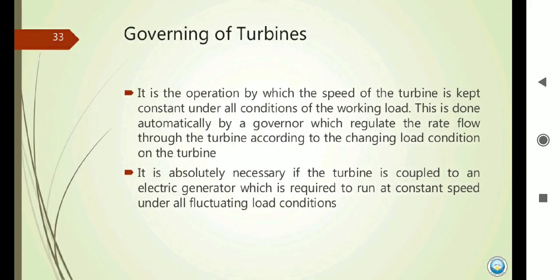Governing of the turbine is also very important. It is the process by which the turbine speed is kept constant under all conditions of working load. This is done automatically by a governor, which varies the water flow through the turbine according to changing load conditions. Governing is absolutely necessary when the turbine is coupled to an electric generator, which requires constant speed.